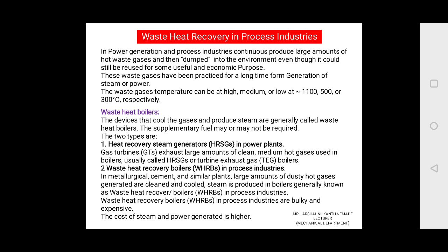The waste gas temperature can be high, medium or low, at 1100, 500 or 300 degrees Celsius respectively. Waste heat boilers, the devices that cool the gases and produce the steam, are generally called waste heat boilers. The supplementary fuel may or may not be required.